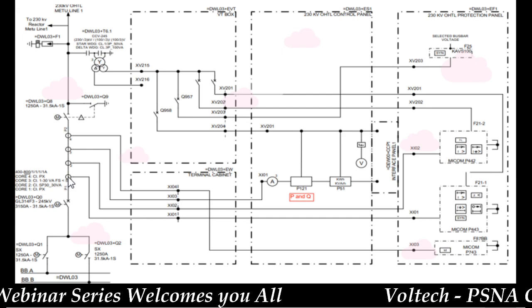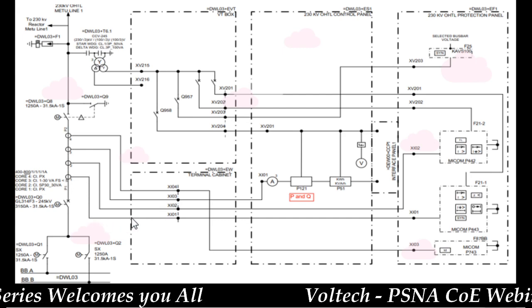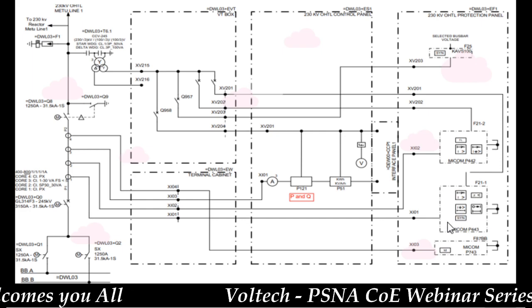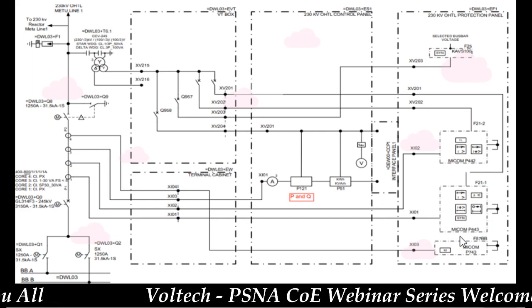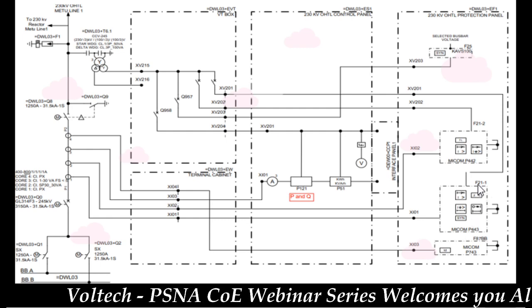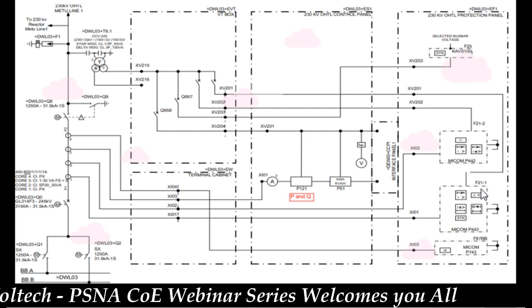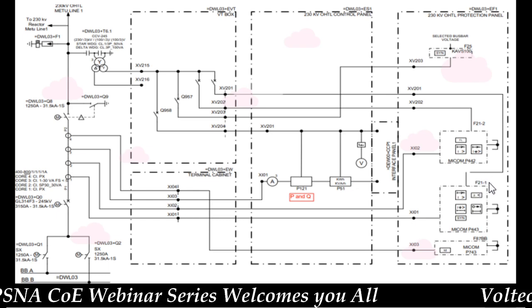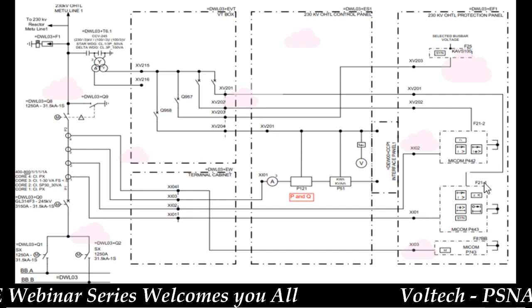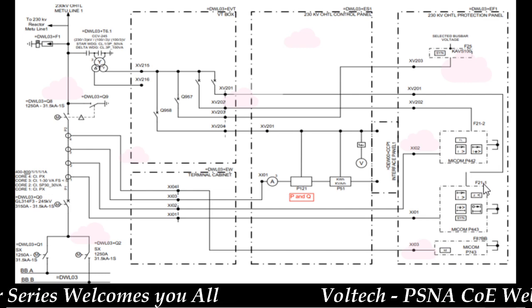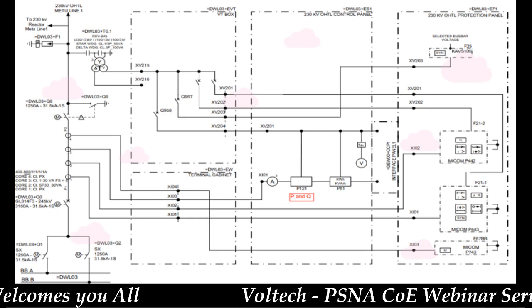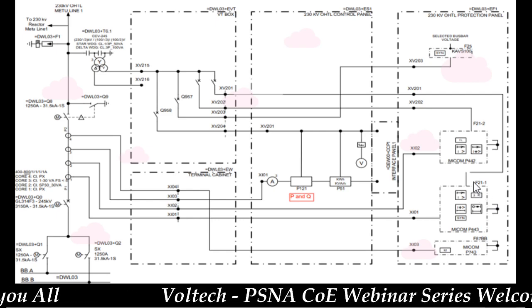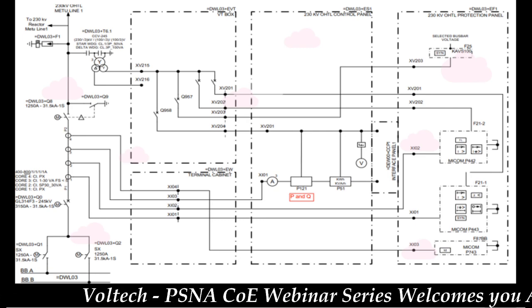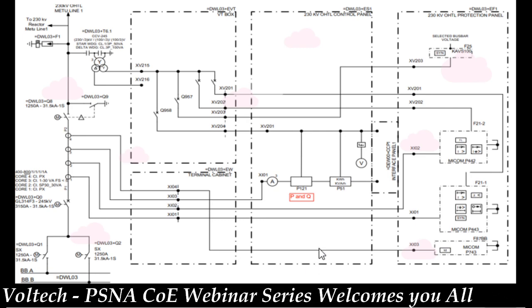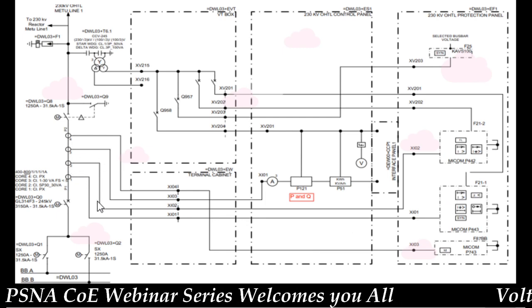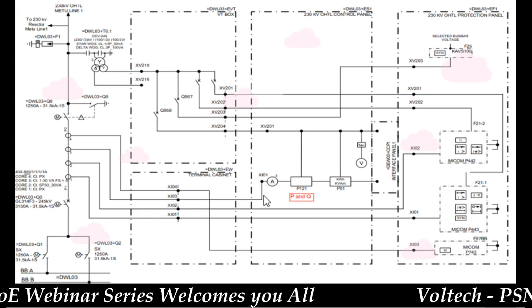So here we can say core 1. We trace core 1 connecting in the protection panel. It's connected with one relay. One relay means the relay having the name F21. We saw that 21 means a distance protection relay, from the ANSI codes. That's why I'm saying the ANSI code is very important. So just go through the ANSI codes. What are the ANSI codes we are using in power systems? I mentioned them in the slides. And next, a different CT is going to different protection and also the metering.